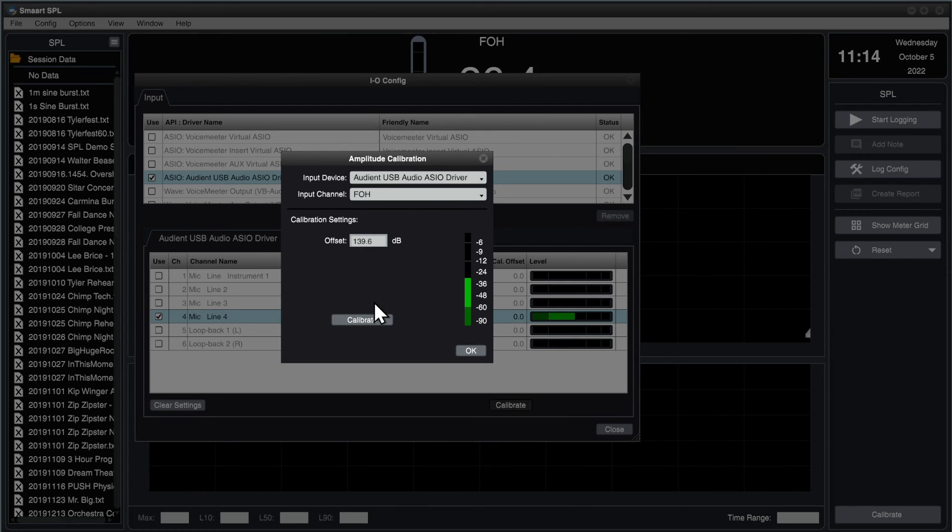The resulting offset value represents the highest sound level that this configuration can measure without overloading the analog-to-digital converter.